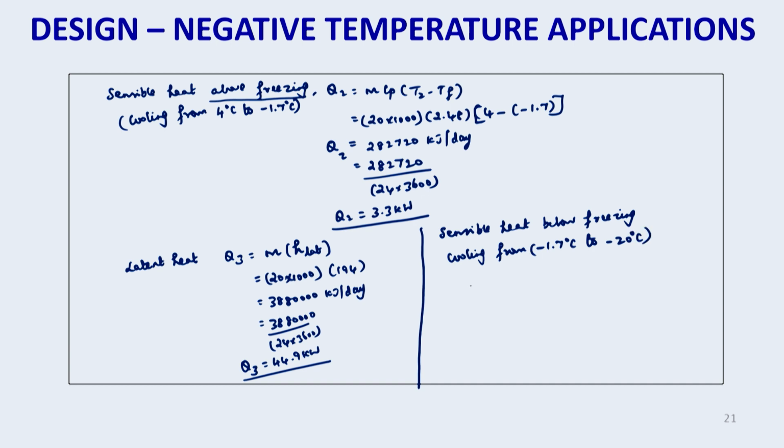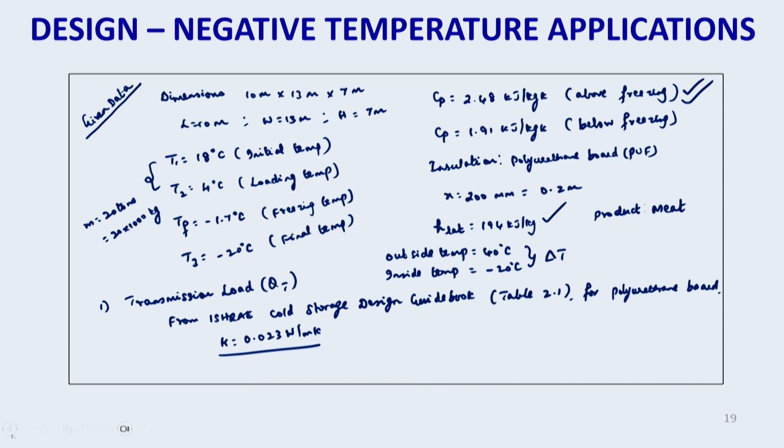So this will be Q4, sorry, Q4 is equal to M into Cp into Tf minus T3, cooling from the freezing point till minus 20, that is the storage temperature.